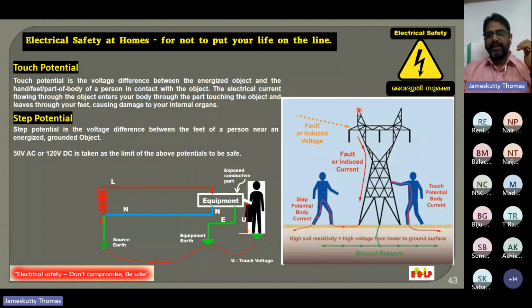In this picture, the tower has a faulty or induced voltage due to insulator failure or something similar, meaning its surface has voltage. If a person standing here touches the tower, current will pass through his body. This happens because he touched the tower, and that is called touch potential. When he touched the tower, a touch potential developed, and because of it, current flowed through his body, causing electrocution.